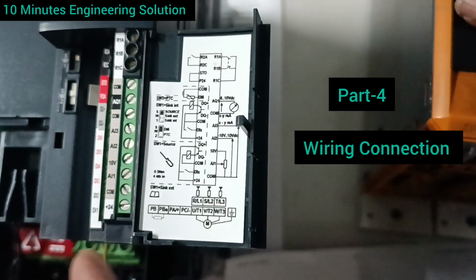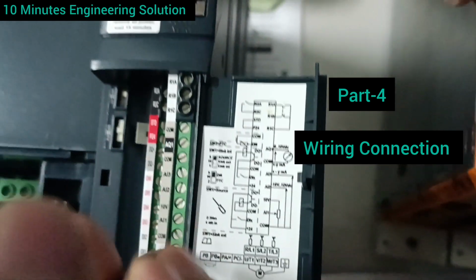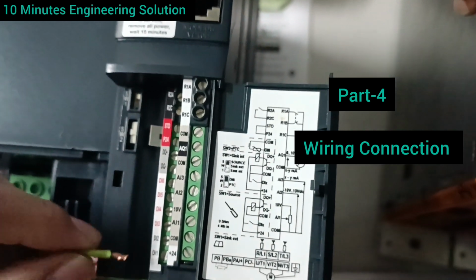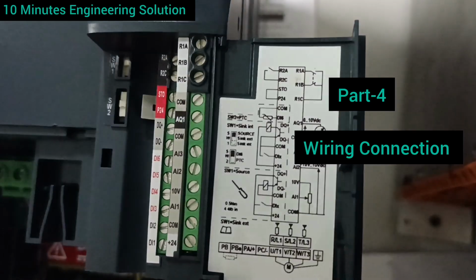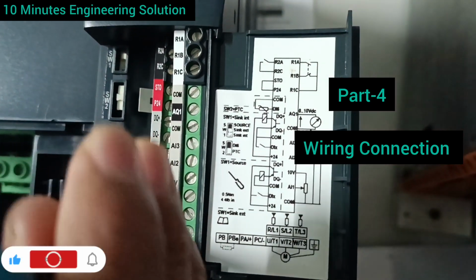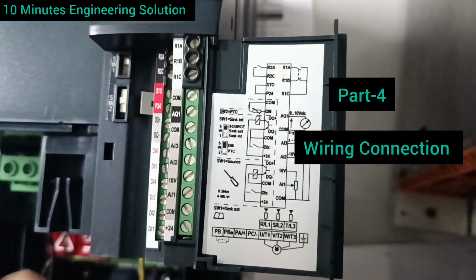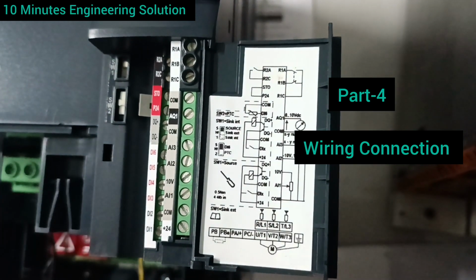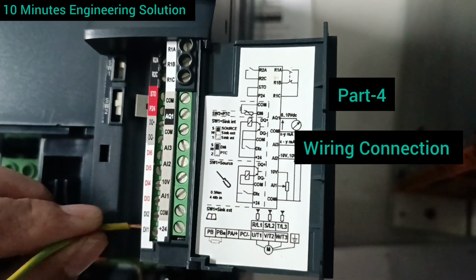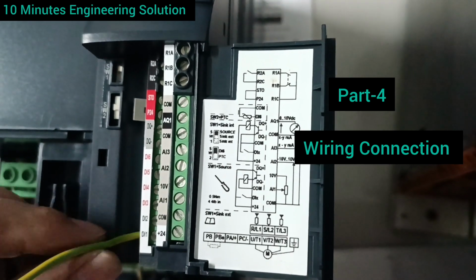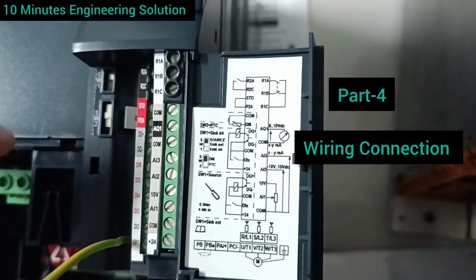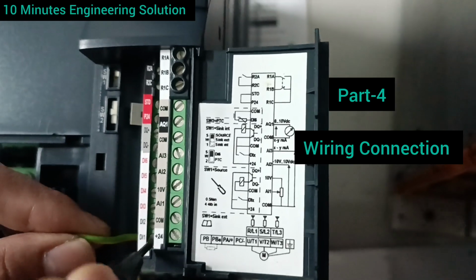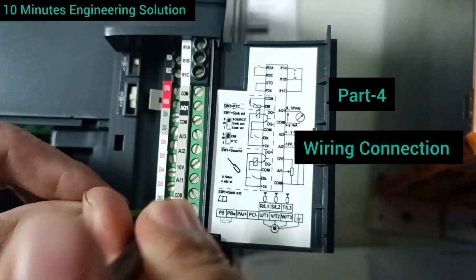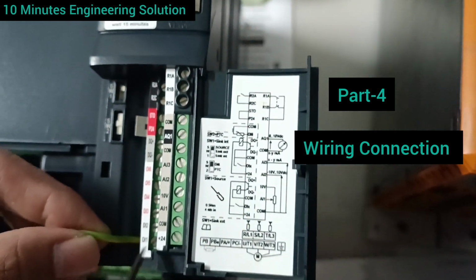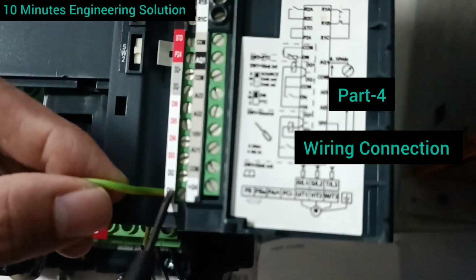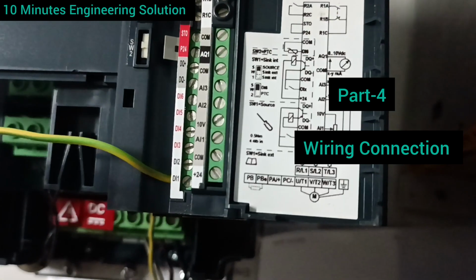Now I'm going to part 4. This is the wiring configurations and wiring connections. So I'm going to start the connections. First of all, I'm connecting DI1 to the switching signal for plus 24. I'm mentioning here that plus 24 to DI1 is just given a short jumper here. But when you use it in your system, you have a switching system. For example, when you want to run one system, you make a switching of 24 to DI1.